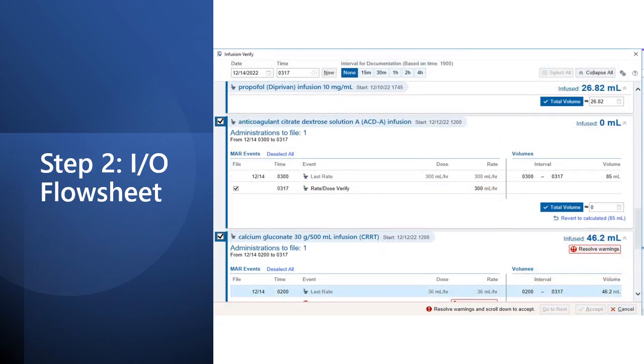On the intake and output flow sheet, when you do the infusion verify all, the default for the citrate is to suggest whatever rate it was ordered as the volume. We've put in a ticket for it not to document that volume, but because I don't know when that's going to be fulfilled, right now we are teaching people to just put 0 there, because remember, citrate is on the white pre-blood pump, or PBP, of the CRRT machine, and that volume is never delivered to the patient.